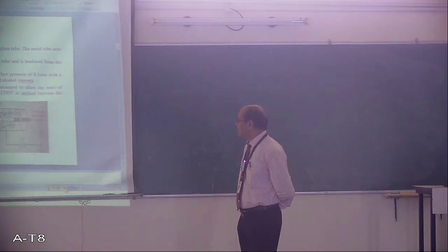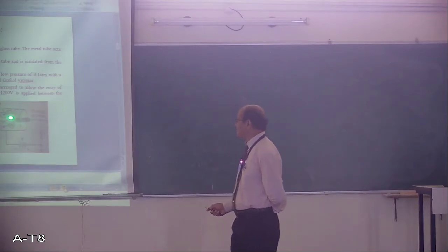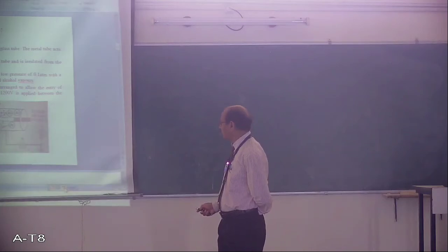However, at the center, a fine tungsten wire runs through the center of the tube, along its axis. And that is usually made of tungsten, and that acts as the anode. So it is connected to the anode, means positive terminal, and the tube body is connected to the negative terminal. High voltage is applied, of the order of 1200 volt. Very high voltage is applied.